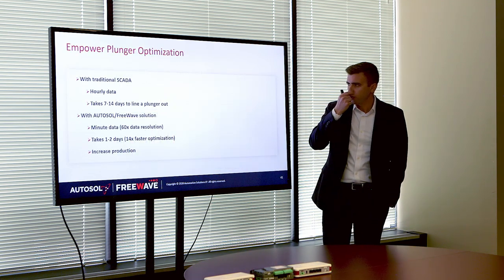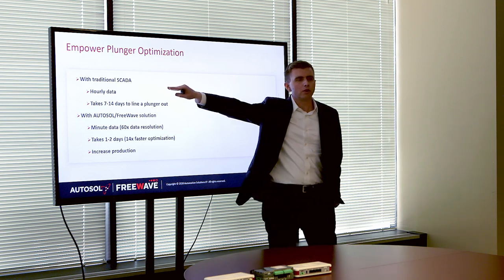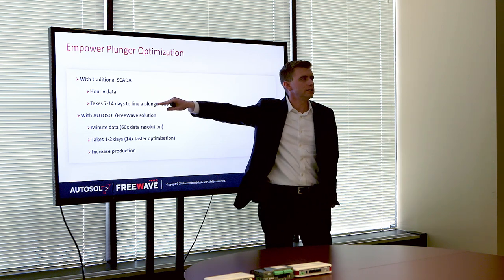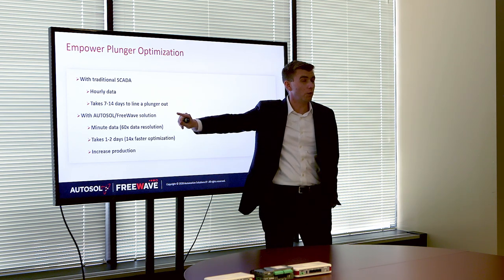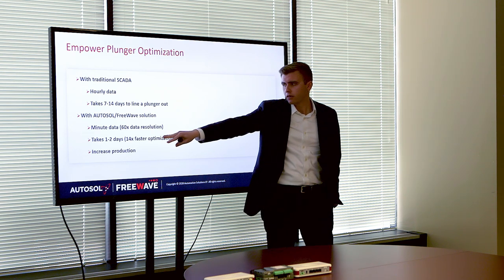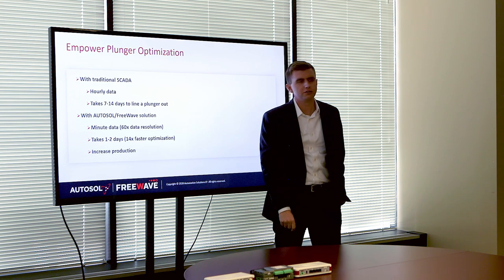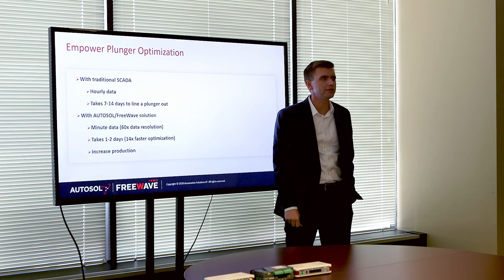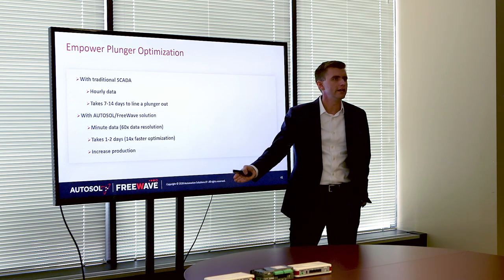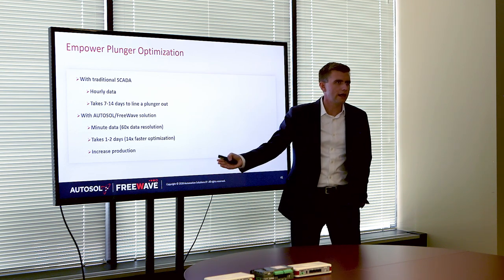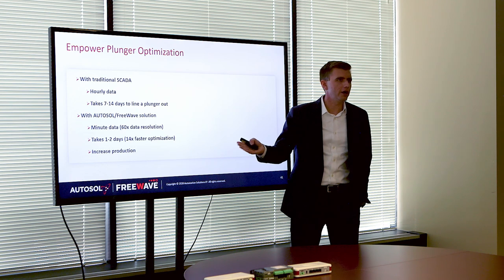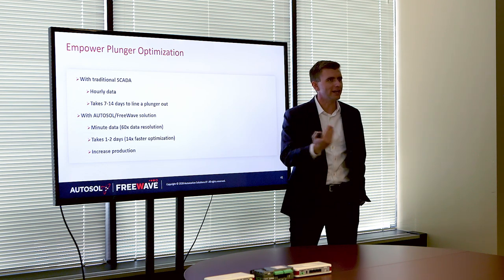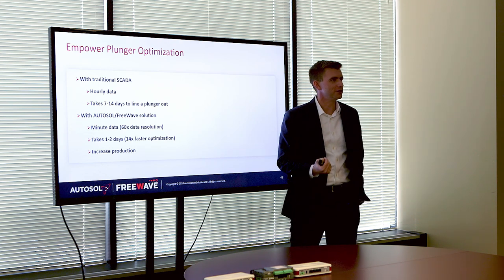With traditional SCADA: one-hour polling, 7 to 14 days optimization cycle. With Edge ACM: one-minute polling on what they cared about, and one to two day optimization decisions. Ultimately this helped them increase production, and that's where our legal ability to share information ends on this particular case.